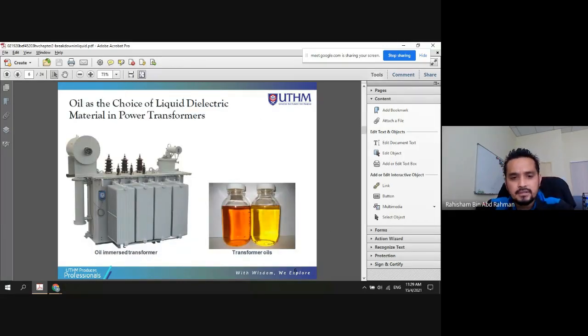For example, we have the transformer oil. Imagine how we can use solid dielectric material to fill up the transformer while it is in the tank like this one. For some other purposes, this needs to serve as a coolant. We need to provide the cooling system for the transformer, and we need convection, the movement of the oil within the transformer. We cannot go for something that is static.